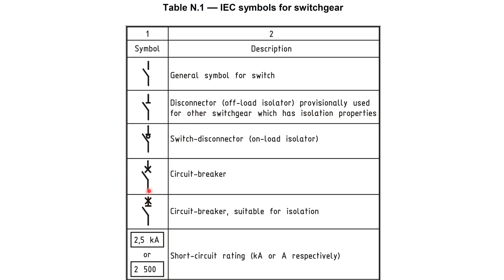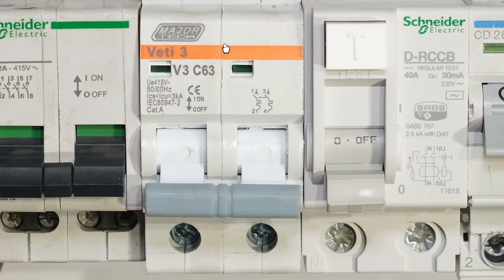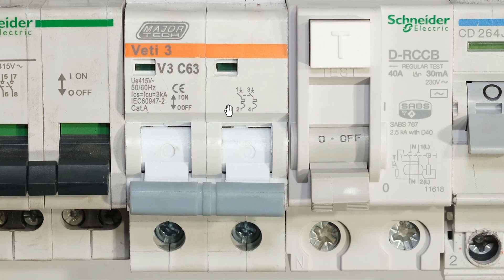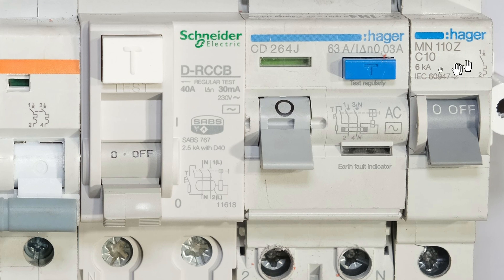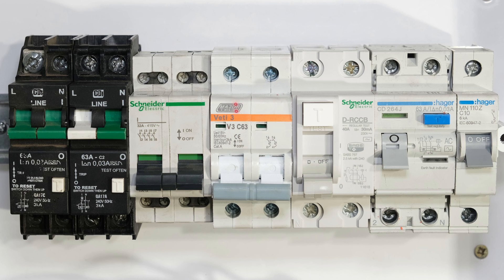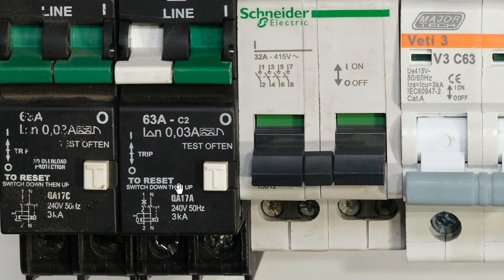Having a look at the circuit breaker symbol — I'm also going to bring your attention to the circuit breaker suitable for isolation. Notice the only difference is the line at the bottom. Over here, we have a double pole circuit breaker, which is also an onload isolator, so this offers both functions. And then over here, we have a circuit breaker rated at 10 amps, so if a current of more than 10 amps is trying to flow through the circuit breaker, it will operate, disconnecting that current. In this double pole circuit breaker, the same applies — it will open both terminals, with maybe a live here and a neutral here. And the circuit breaker will disconnect both. If I show you this one over here, this is an earth leakage circuit breaker, and there's an X telling me it also operates as a circuit breaker for fault conditions.